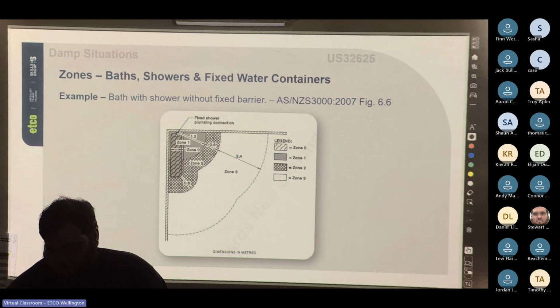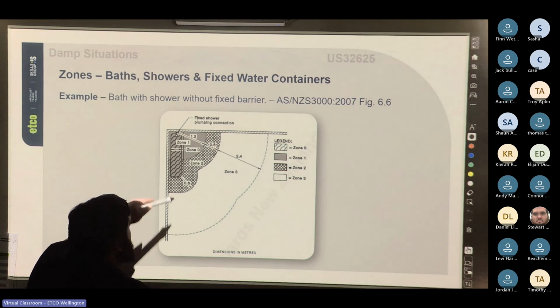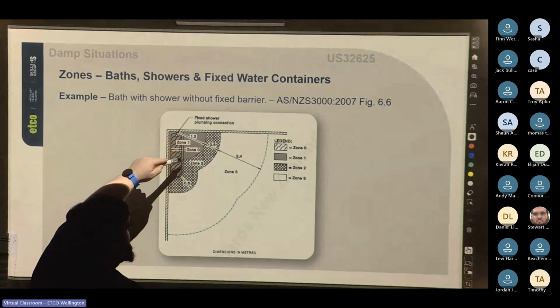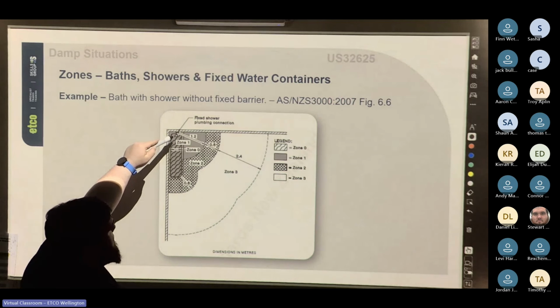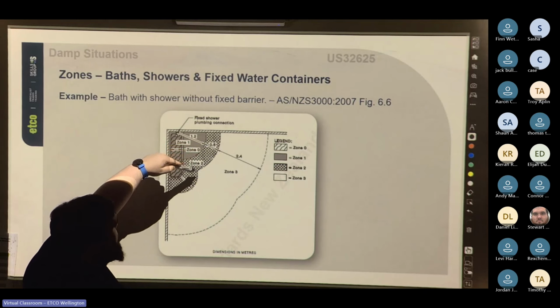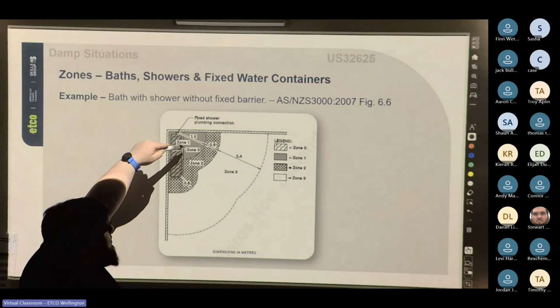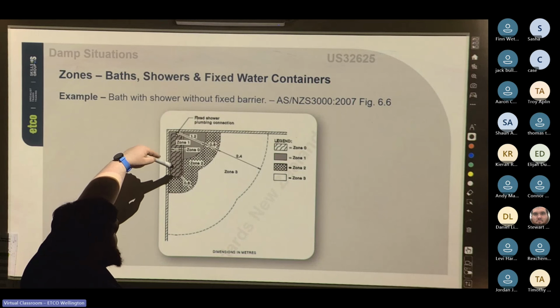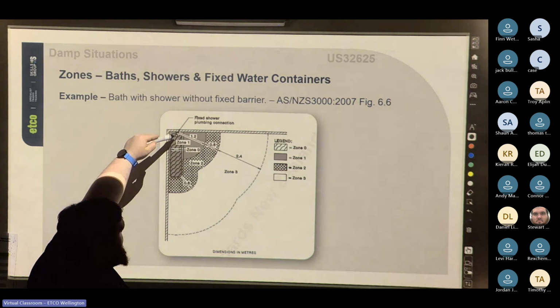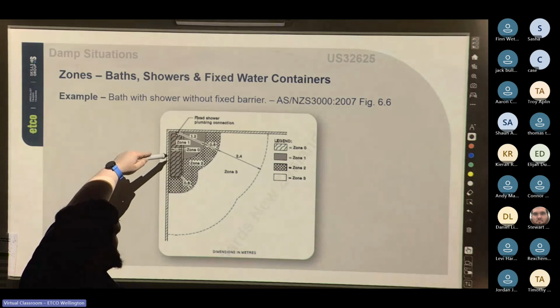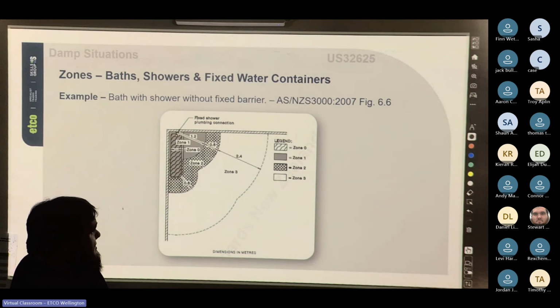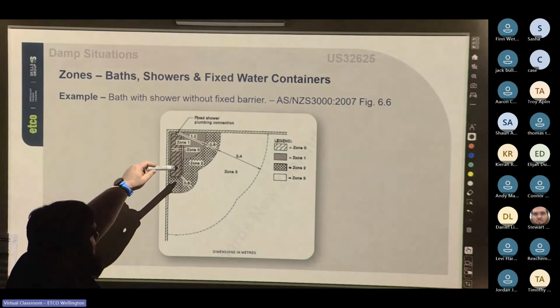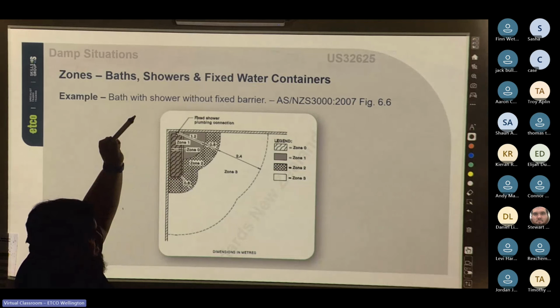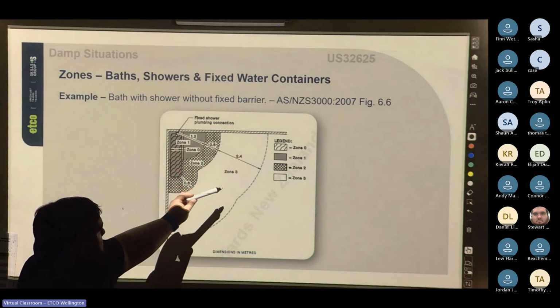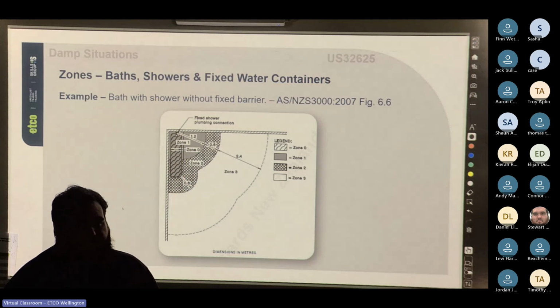So we go to 6.6. It's a bath with a shower without a fixed barrier. As you can see, zone 0 is the bathtub water itself, as well as this 1.2 meter radius from the fixed shower plumbing connection. Zone 2 must move to be 0.6 away from all of these different areas in zone 1. So zone 0 is the water itself, zone 1 is 1.2 meters out from the shower head and the bathtub water up to a height of 2.25 meters. Zone 2 is 0.6 meters from the edge of zone 1, up to 2.25 meters. And zone 3 is 2.4 meters beyond zone 2, up to a height of 2.25 meters.